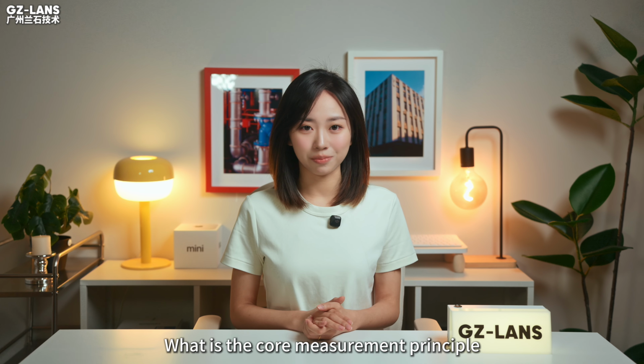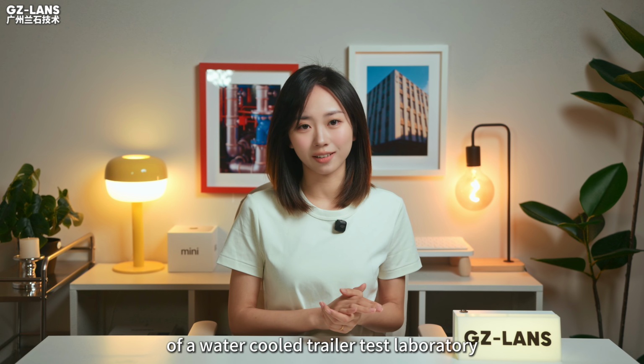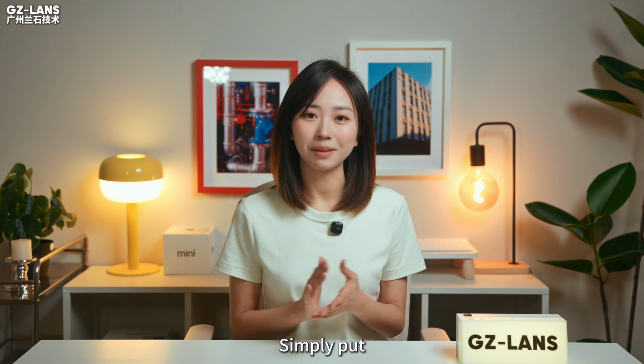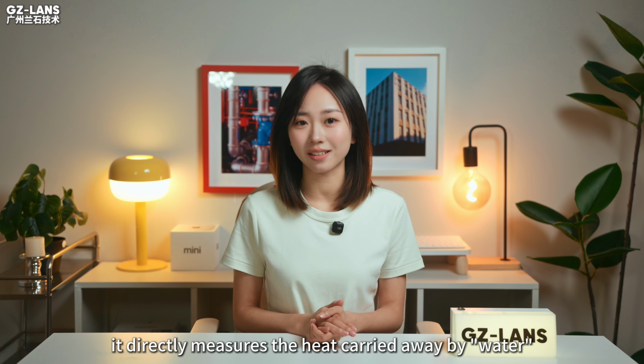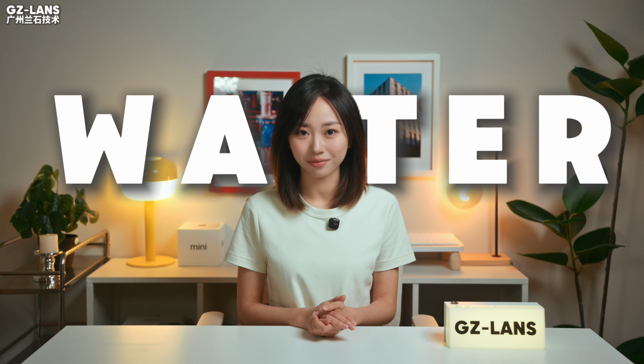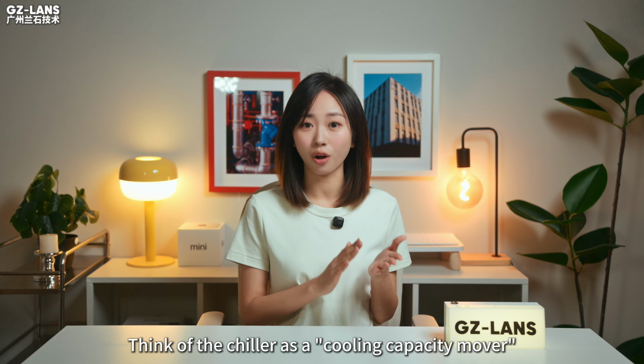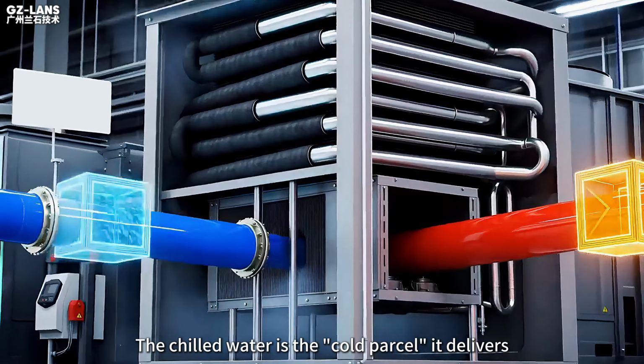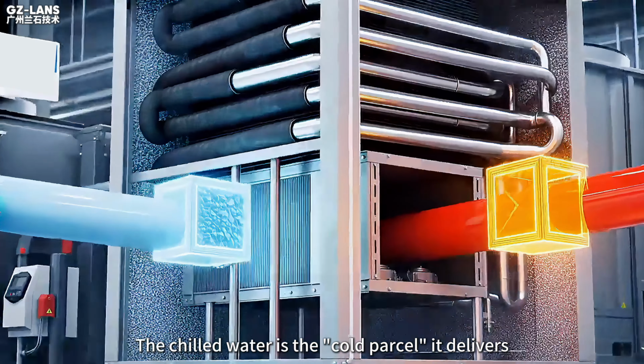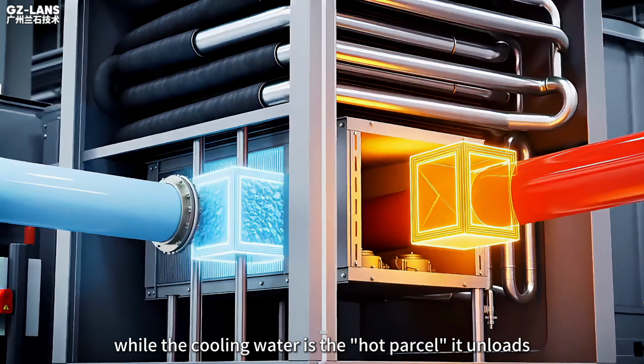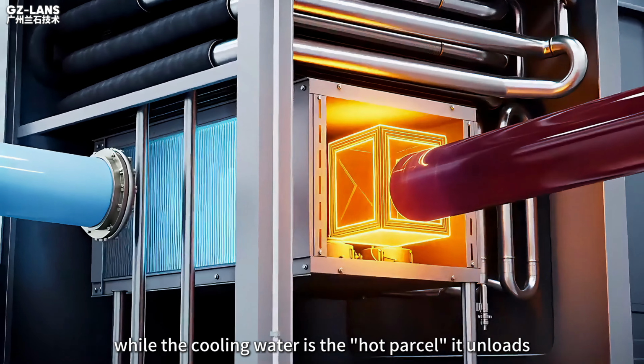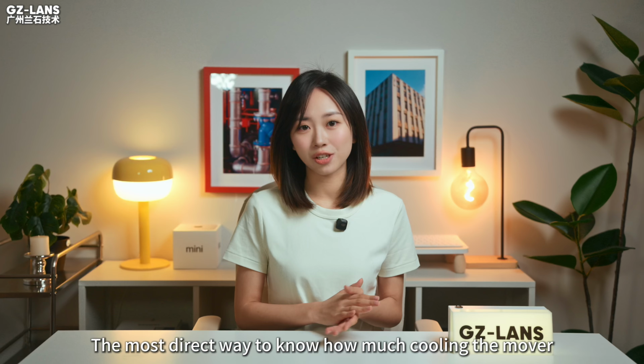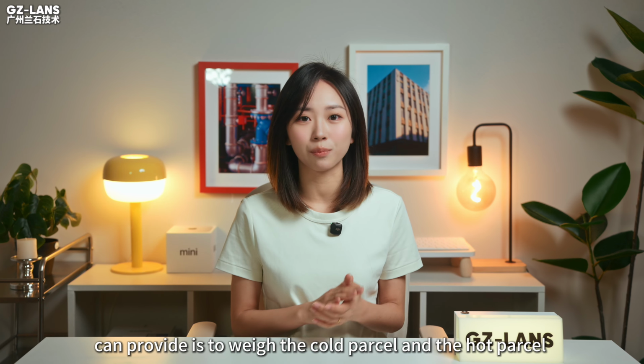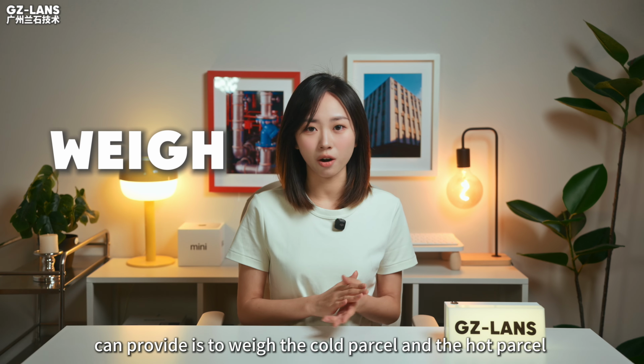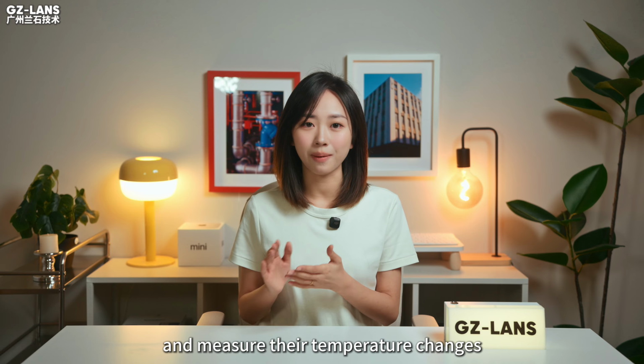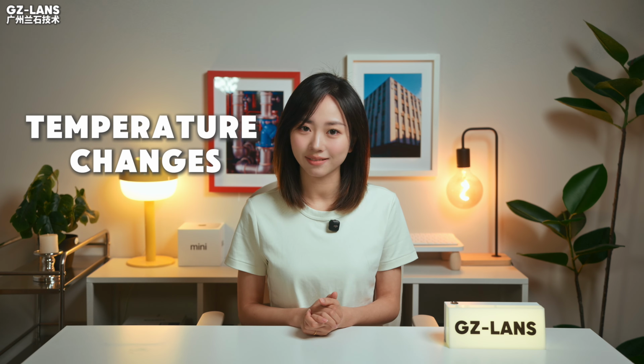What is the core measurement principle of a water-cooled chiller test laboratory? Simply put, it directly measures the heat carried away by water. Think of the chiller as a cooling capacity mover. The chilled water is the cold parcel it delivers, while the cooling water is the hot parcel it unloads. The most direct way to know how much cooling the mover can provide is to weigh the cold parcel and the hot parcel and measure their temperature changes.